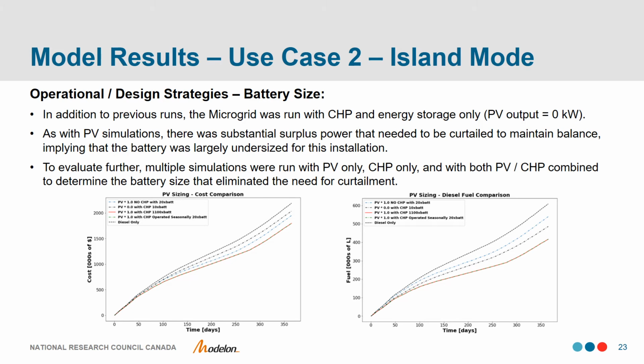The next design consideration is battery size. In all previous runs, looking at CHP operating only or PV operating only, there was always substantial surplus power that needed to be curtailed in order to maintain balance, implying that the battery was largely undersized for this installation. To evaluate further, multiple simulations were run with PV only, CHP only, and with both PV and CHP combined to determine the battery size that eliminated the need for curtailment. With the PV operating alone without CHP, we needed 20 times the original battery size. For CHP operating alone, we needed 10 times the original battery size. For both PV and CHP combined, we needed 1,100 times the original battery size. So we're getting to a very expensive battery.